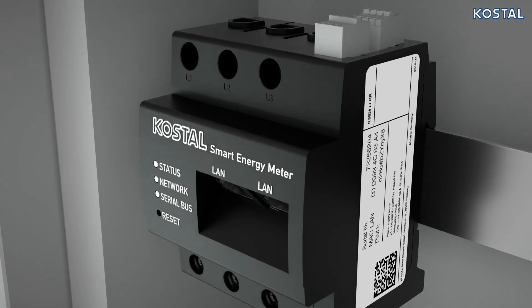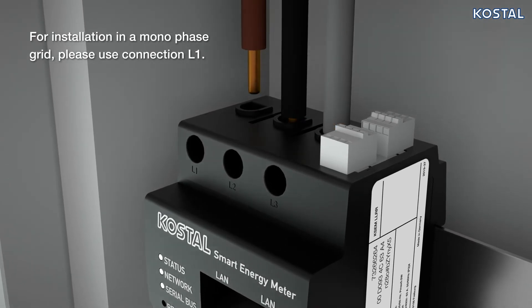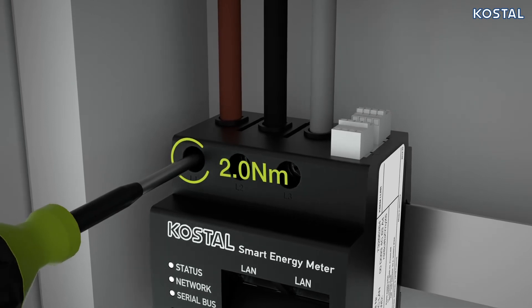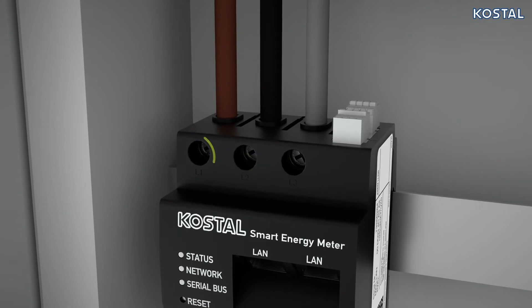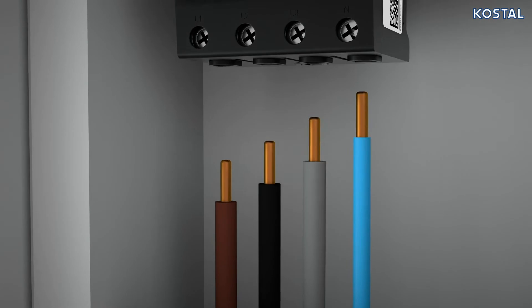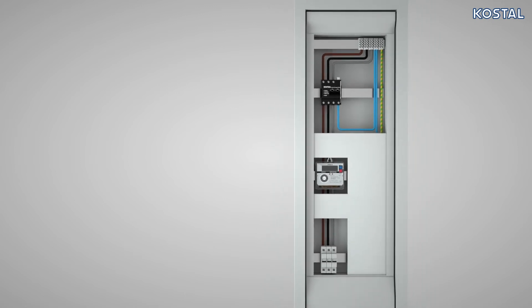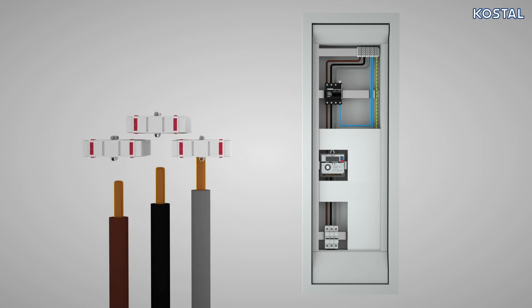Now connect the wires to the KOSTAL Smart Energy Meter. Note the connection cross-section and torque for screw terminals. Check the amount of power needed before installing. The Smart Energy Meter has a capacity of 63 amps. Should the system require more power, please use an external transformer. Please refer to the information provided in the Quick Start Guide enclosed for more details.